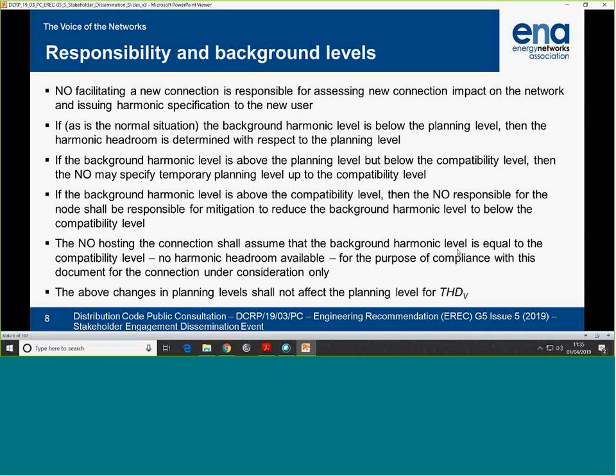But there are also cases where the background exceeds the compatibility level. Then the NO facilitating the connection is responsible to mitigate that condition. Because according to this, and the D-code and the G-code, 95 percentile, 90% of time, and in some interpretations, a location can be above the planning or compatibility level. Therefore, NO is able to mitigate that.